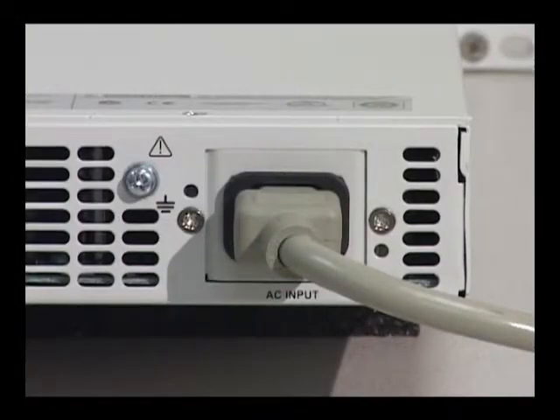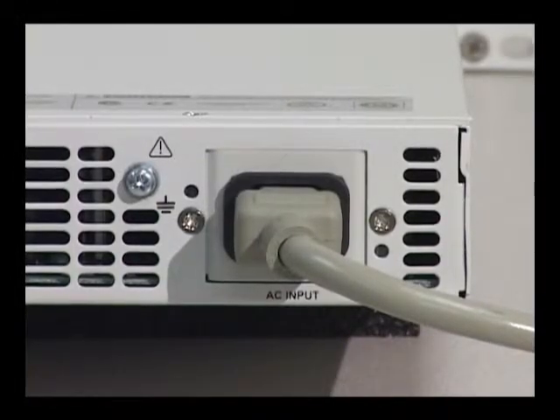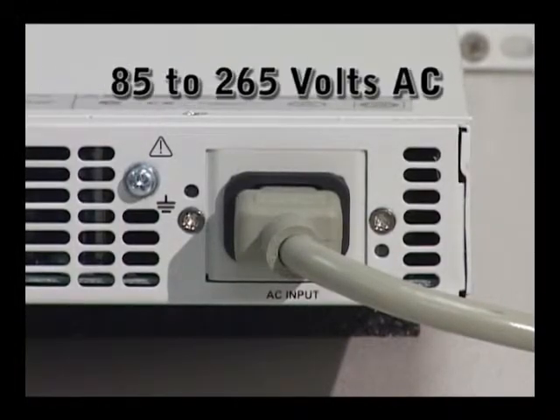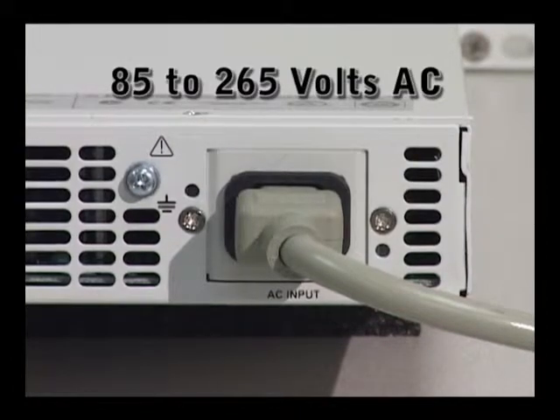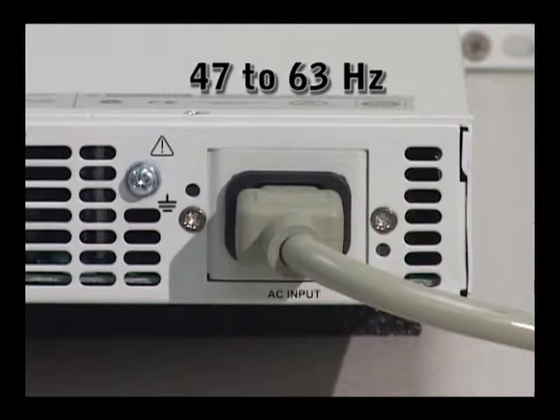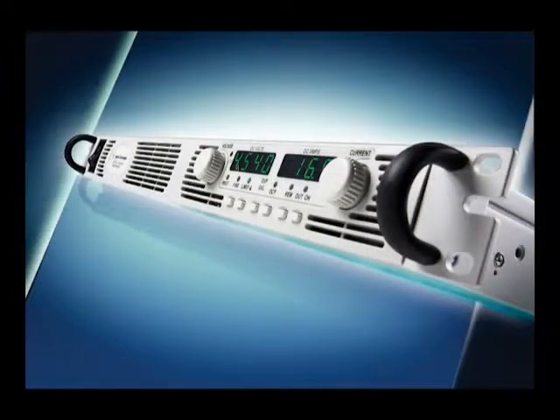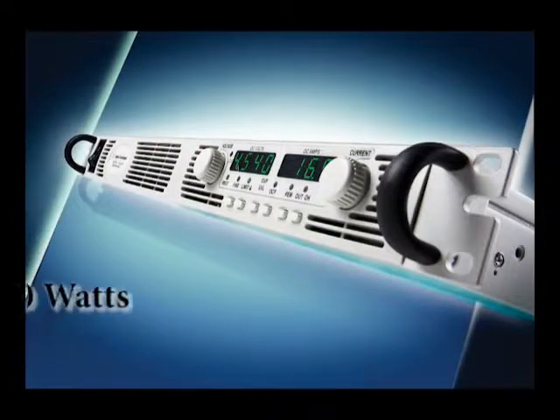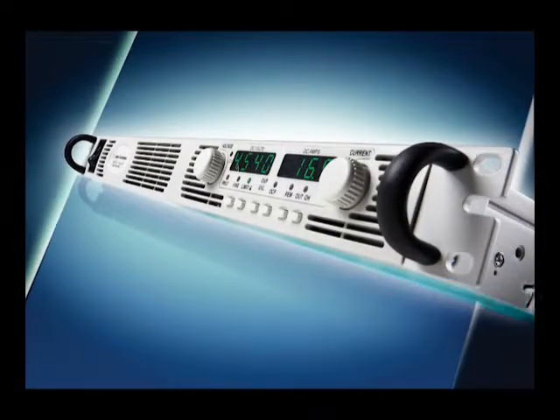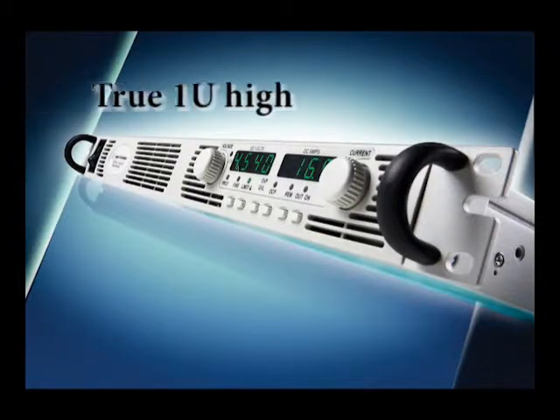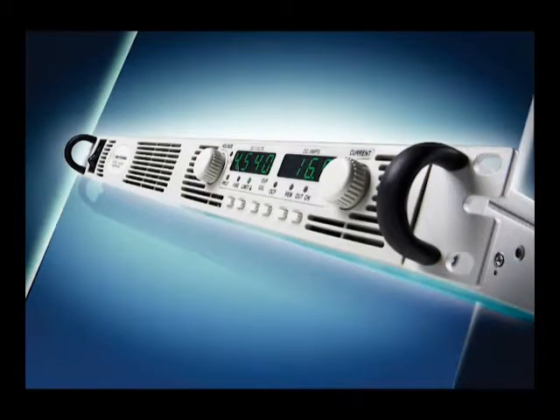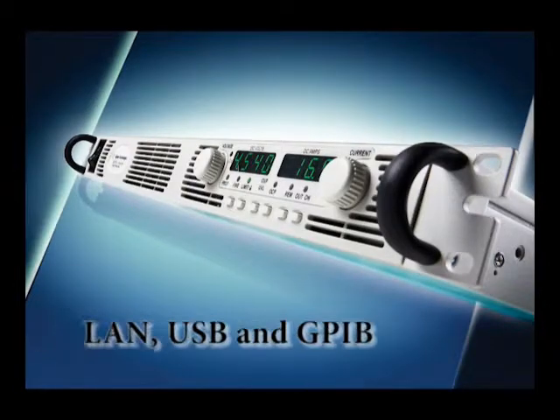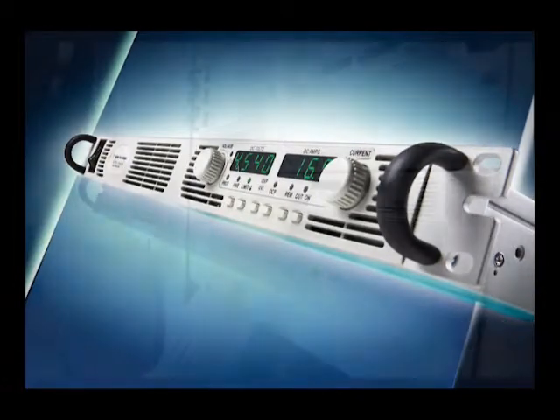All N5700 models have a universal AC power input that operates from 85 to 265 volts AC, 47 to 63 hertz. The N5700 series of 750 watt and 1500 watt DC power supplies provide affordable, reliable power in a high density 1U high package, and give you the flexibility of LAN, USB and GPIB interfaces.